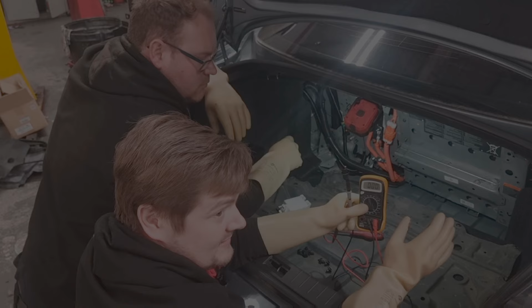If you're using a multimeter to check for voltage, i.e. to check a circuit's safe, obviously if you put this in the wrong place, this is going to become an amp meter and therefore have a dead short. Hopefully the fuse is going to pop before it does any damage, but it's just something to bear in mind. Sometimes the probe testers are a little better because you can't put them in the wrong setting. Fortunately we've got a negative here and a positive next to it. Even though they're separate circuits, they are all still the same, so that's quite helpful.